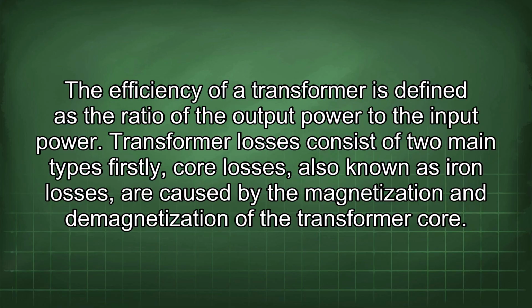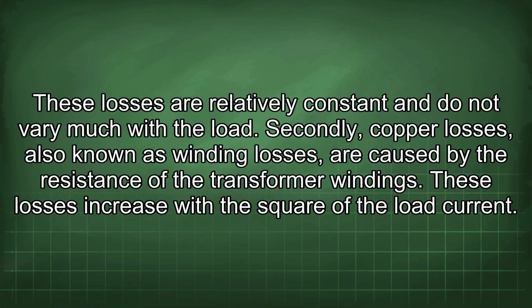Transformer losses consist of two main types. Firstly, core losses, also known as iron losses, are caused by the magnetization and demagnetization of the transformer core. These losses are relatively constant and do not vary much with the load. Secondly, copper losses, also known as winding losses, are caused by the resistance of the transformer windings. These losses increase with the square of the load current.